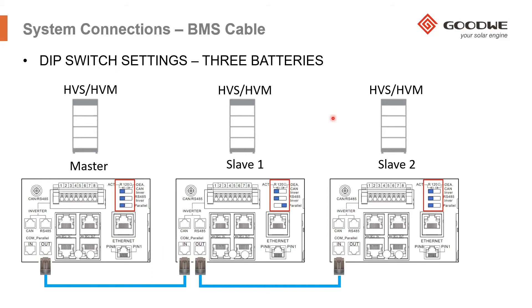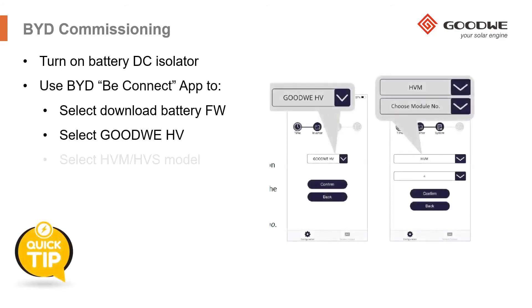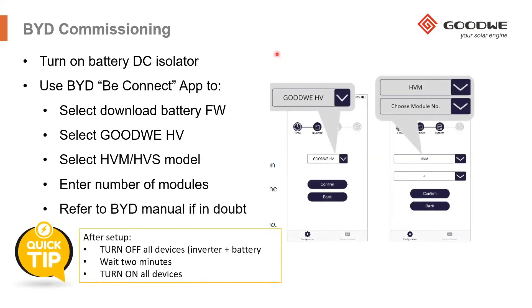Once you've connected the BMS cable, set up the DIP switches, and connected the Ethernet cables if you're using more than one battery, you can start commissioning the PV plant. For commissioning you need the PV Master app. But before that, you can turn on the battery DC isolator of the BMU. What you should be using for commissioning of the battery is the BYD Be Connect app, which you can download from the Google Play Store and also the Apple App Store.